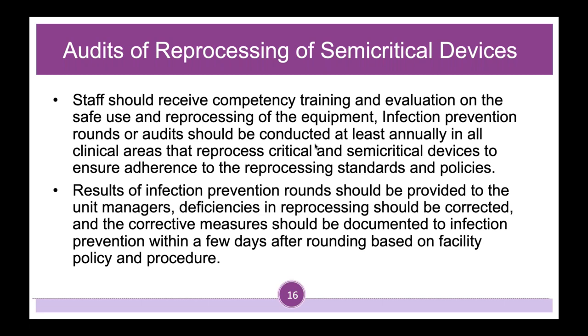So, audits of reprocessing of semi-critical devices: staff should receive competency training and evaluation on the safe use and reprocessing of the equipment. Infection prevention rounds or audits should be conducted at least annually in all clinical areas that reprocess critical and semi-critical devices to ensure adherence to reprocessing standards and policies. Results of infection prevention rounds should be provided to the unit managers. Deficiencies in reprocessing should be corrected, and the corrective measures should be documented to infection prevention within a few days after rounding, based on facility policy and procedure.